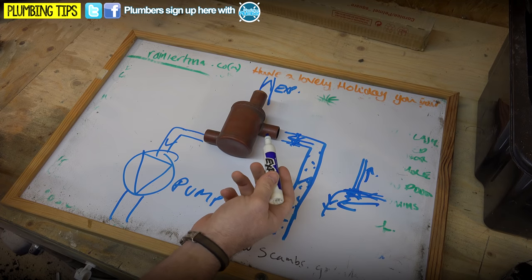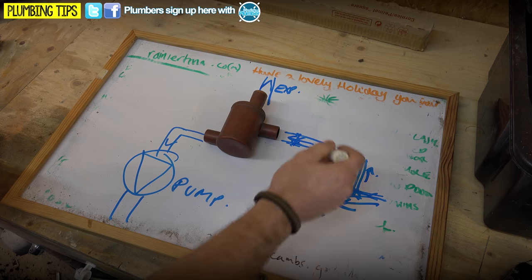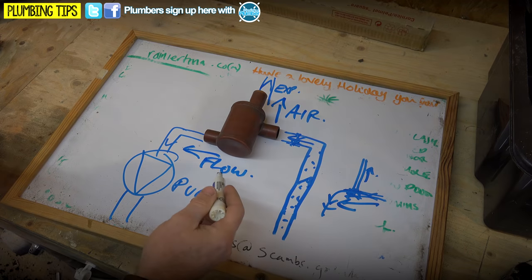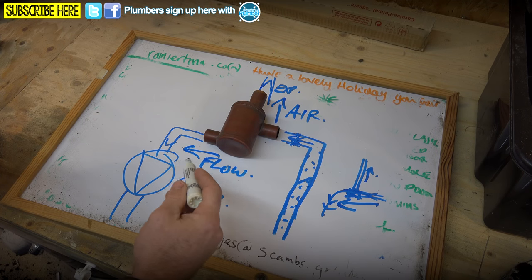So, okay, we've got this size here. This is the size of pipe we've got here, just like that. At the moment, that's the size of area. But we introduce it to this large area here. This is a larger area. See it as like a water break that doesn't reduce the flow around the system. So, you've got this water break here. The water just sits in here. It has just a few seconds to sort of swirl about, and then go off back out. And in those few seconds that it's in there, it can get rid of its air up this pipe here and up to the expansion and out of the way. That's all this is doing here. It's so, so simple. So, we have this air comes in, rushes in, it's kind of slowed down a bit. We get rid of it up here, air out of there, so our flow can go off here, round the system, and be completely deaerated.